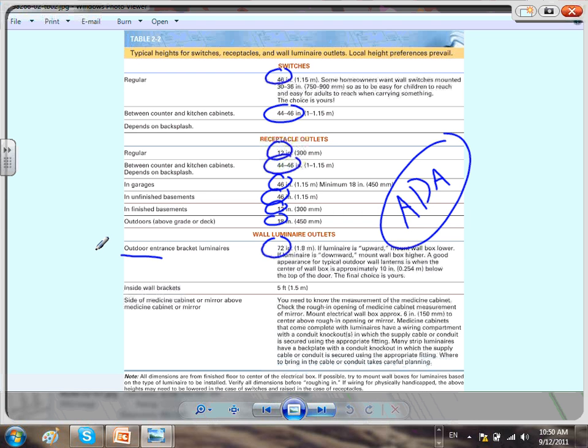A specific note is when I have a receptacle and I put a keynote right next to it because I want my plasma TV outlet to be at 72 inches, or say 55 inches. So I add a keynote saying the receptacle shall be installed at 55 or 72 inches above finished floor, to tell the electrician exactly what I want.